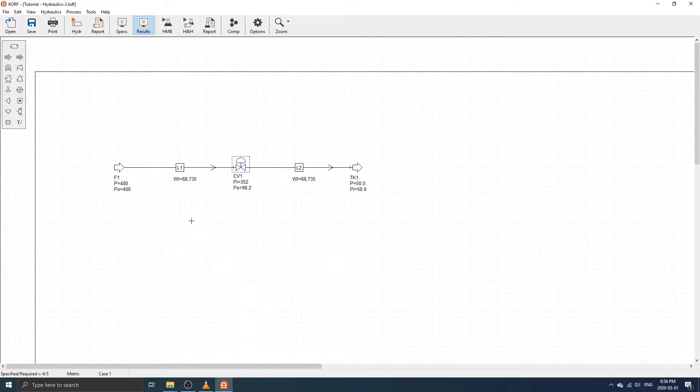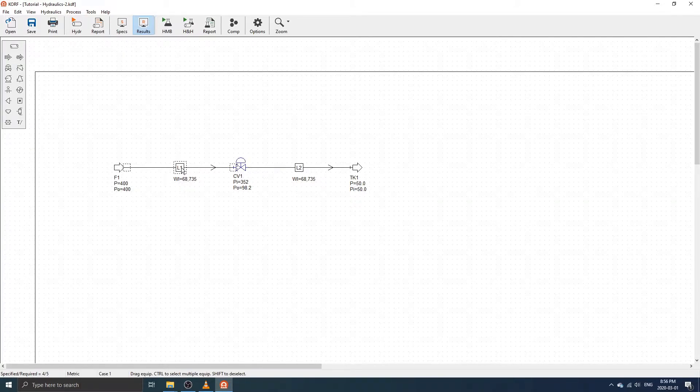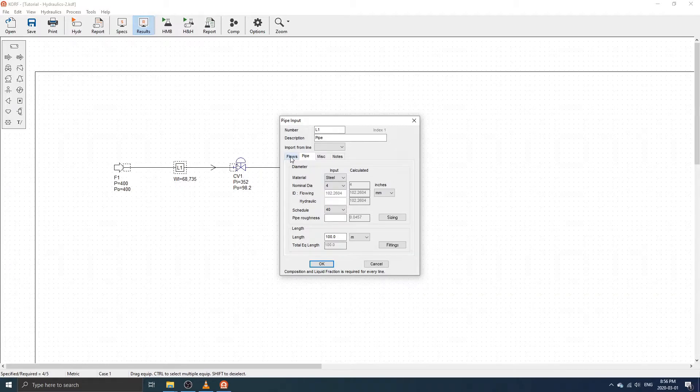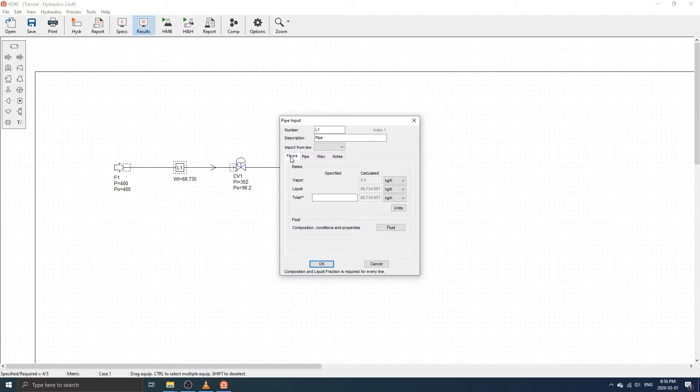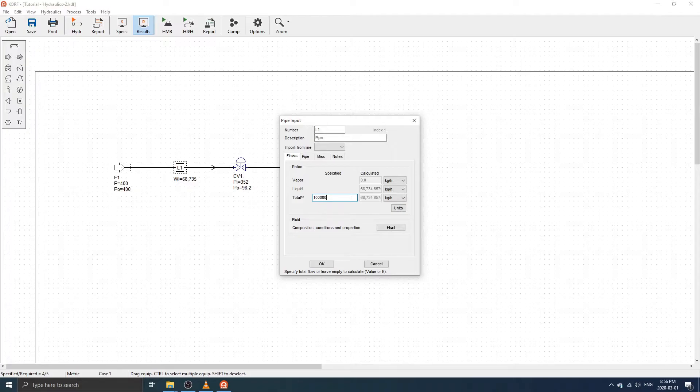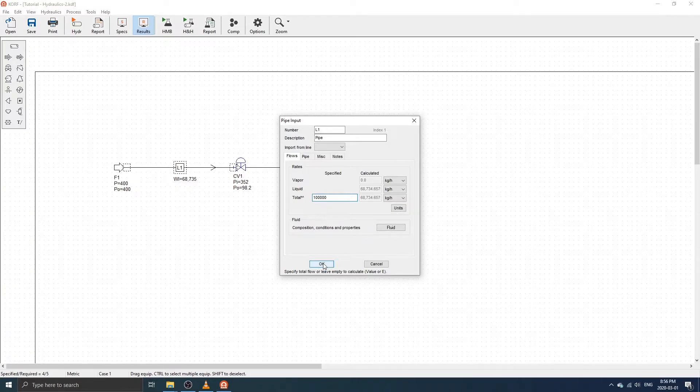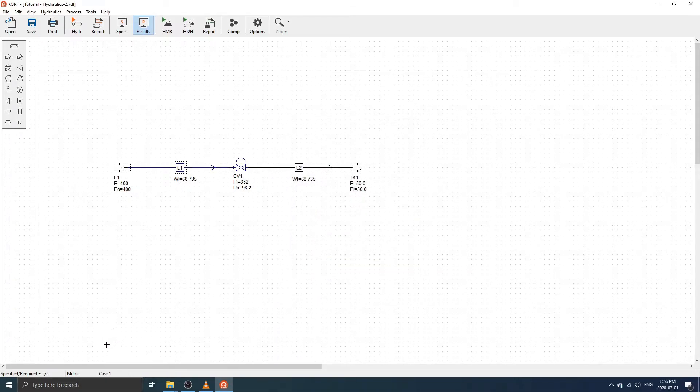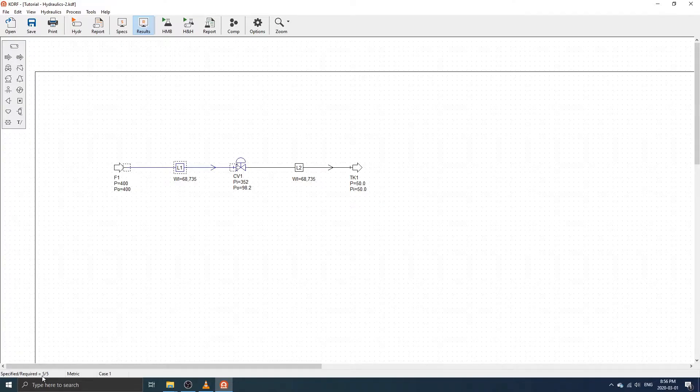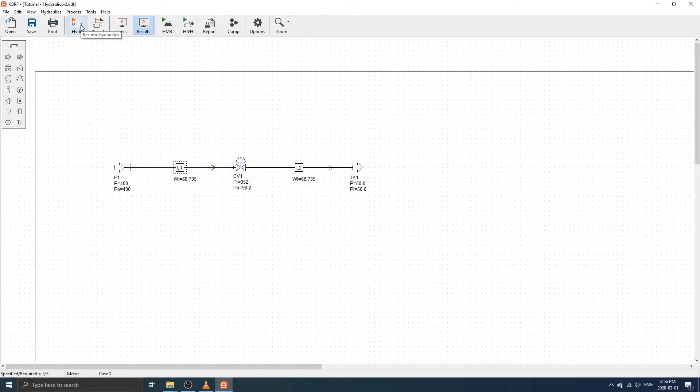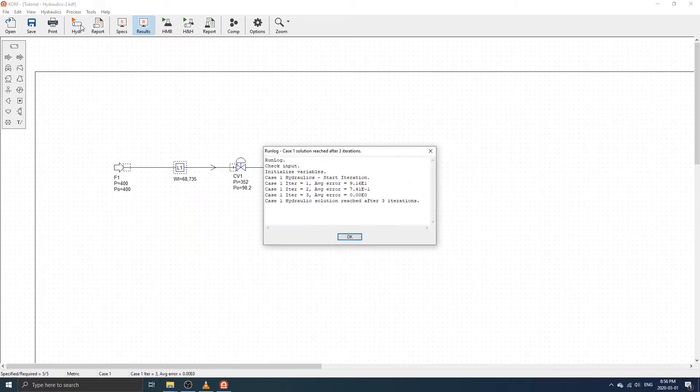Next, double-click on the pipe attached to the control valve inlet. Then, select the flows tab and enter the required mass flow rate. In this example, we will use 100,000 kilograms per hour. Click OK to confirm the change. The status bar now shows that the number of specifications provided is the same as what is required. Click on Hydraulics to rerun the simulation and calculate the valve CV.